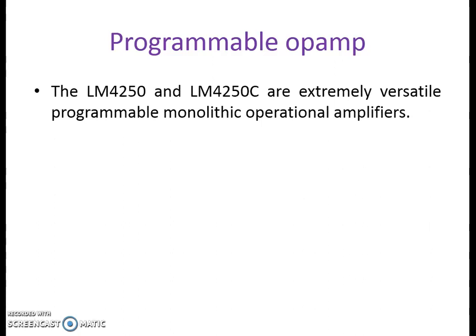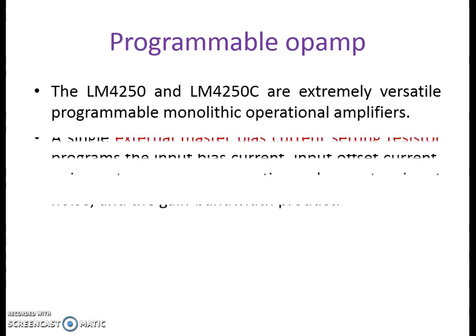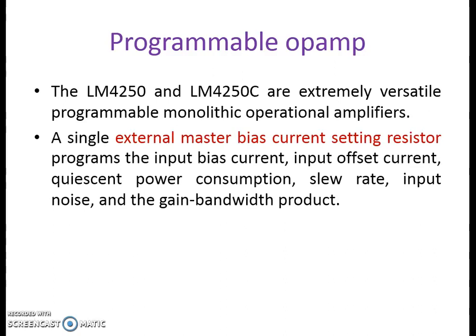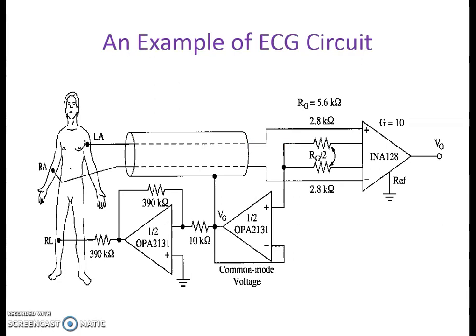Nowadays op-amps used for making the preamplifier or instrumentation amplifier of the ECG machine have a characteristic of programmability. For example, the LM4250 or LM4250C are extremely versatile programmable monolithic operational amplifiers. Programmability means a single external master bias current setting resistor programs the input bias current, input offset current, power consumption, slew rate, input noise, and the gain bandwidth product. The device is truly a general-purpose operational amplifier. In one example ECG circuit, the right arm and left arm are both connected to the instrumentation amplifier, and part of the common mode signal is fed back to the right leg through the right leg driver circuit.